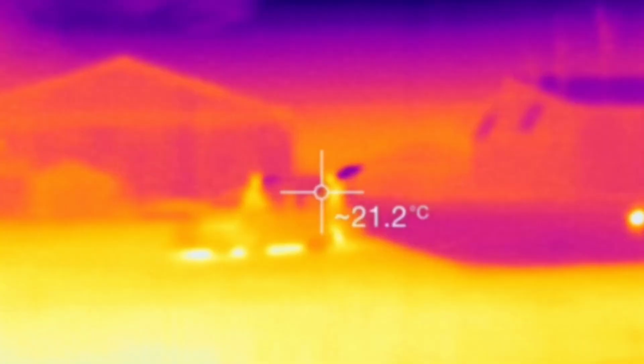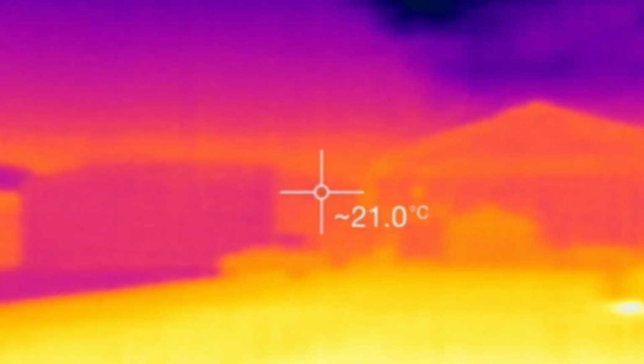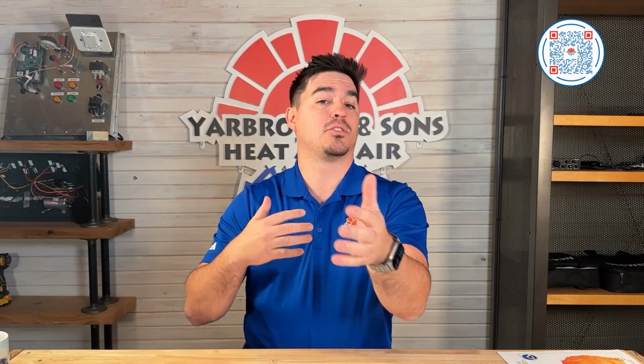What you want to do is design the size of the system to match the heat load on that house. Your home can have a specific heat load during the summer and wintertime, so you want to make sure you match that tonnage to the effective load on your home. Make sure you're not sizing the system by square footage alone, because there are a lot of variables that can affect the heat load on a seasonal basis.